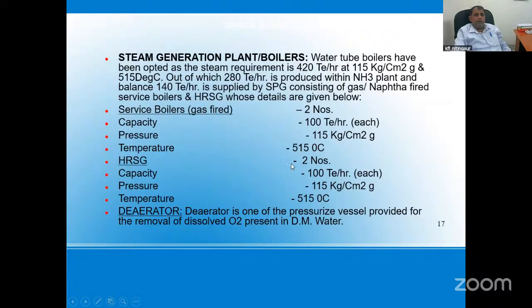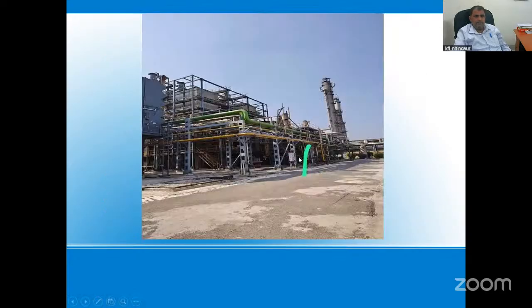And we also have 2 HRSGs, as we explained earlier. The HRSG is directly coupled to the gas turbine, utilizing the exhaust of the gas turbine. That's why it is called HRSG, heat recovery steam generator. Capacity of boiler and HRSG are the same. This is about the boilers' photographs.